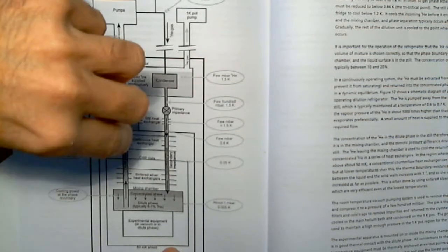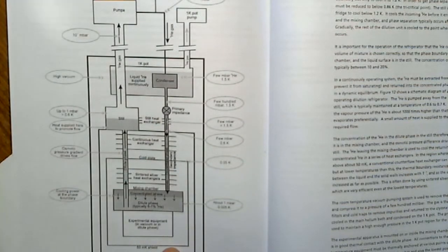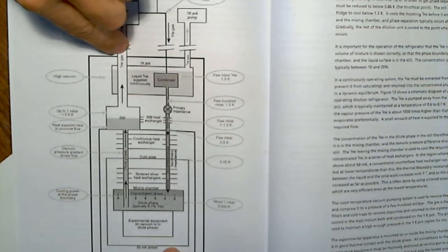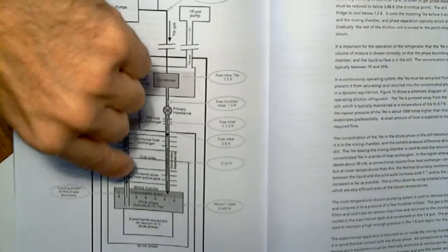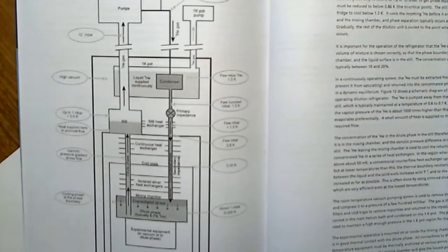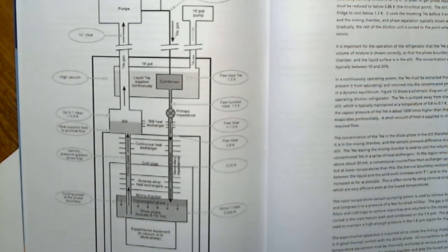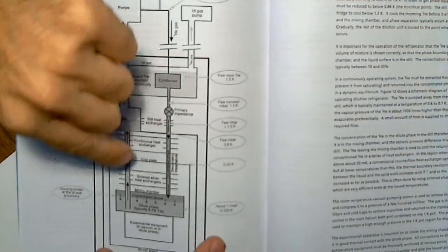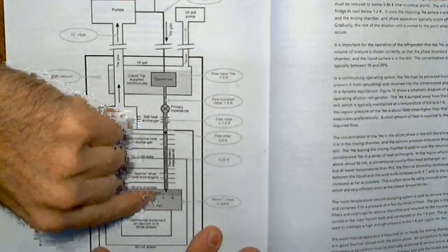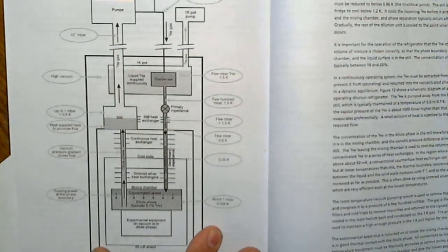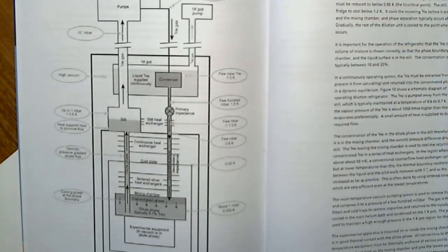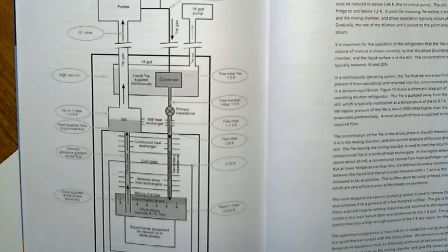At this cold temperature, the vapor pressure from helium-3 is much bigger than from helium-4. That means if you pump out, mostly helium-3 is pumped while the helium-4 stays. Because you are pumping out, you create an osmotic pressure. The helium-3 on the bottom begins to migrate to the other region, because the concentration of helium-3 and helium-4 must stay constant. So you create this osmotic pressure: here you have, say, 6% helium-3, and there 1% helium-3. If you pump out and the 1% drops toward 0.9%, it has to stay constant, so other helium-3 atoms migrate to keep it at 1%. This migration creates the osmotic pressure from the bottom.